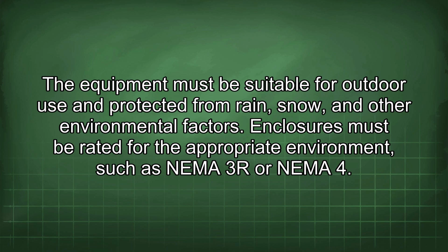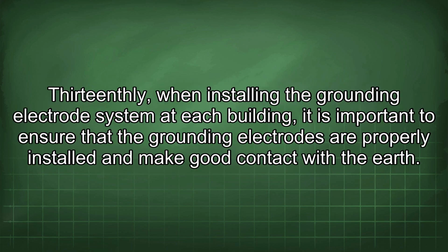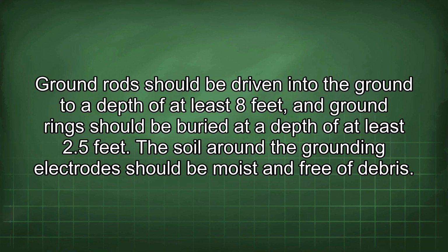The equipment must be suitable for outdoor use and protected from rain, snow, and other environmental factors. Enclosures must be rated for the appropriate environment, such as NEMA 3R or NEMA 4. 13thly, when installing the grounding electrode system at each building, it is important to ensure that the grounding electrodes are properly installed and make good contact with the earth. Ground rods should be driven into the ground to a depth of at least 8 feet, and ground rings should be buried at a depth of at least 2.5 feet. The soil around the grounding electrodes should be moist and free of debris.